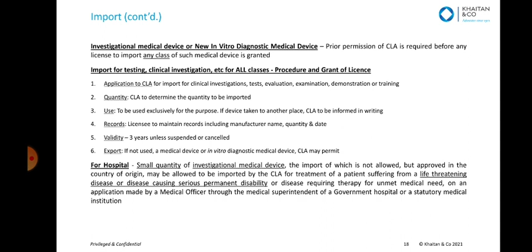Clinical investigation is again specifically provided for medical devices and in vitro diagnostic medical devices, and for medical devices you need central licensing authority approval, which is CDSCO approval. An ethics committee needs to be appointed and needs to approve, and that ethics committee is governed by the Drugs and Cosmetics Rules. There's a concept of pilot clinical investigation and pivotal clinical investigation. Pilot is where the device is used for the first time on humans, on very few human subjects, just to get data, and pivotal clinical investigation uses a larger number of humans to confirm the data which is generated.